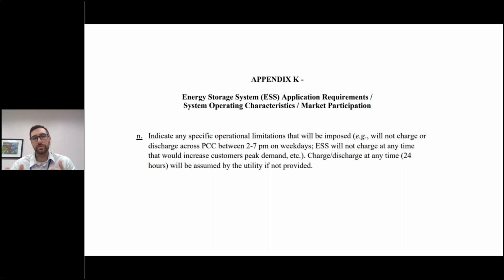And what we've been able to do through the standard interconnection is add what we call the Appendix K process to the interconnection process, where we allow the energy storage project to submit an operational profile and charge discharge cycles, any constraints they want to put on the interconnection study through this question N under Appendix K, and submit that information to the utility to help inform the utility's dispatch study for the energy storage system.